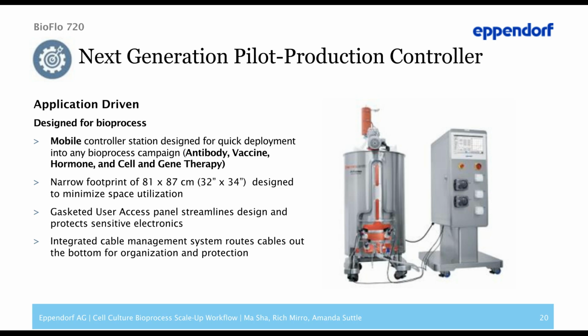The user access panel, shown on the instrument on the left-hand side, closed in the image, streamlines and protects sensitive electronics. In the previous screen, you could see it open where an operator was connecting sensors. That panel allows cables to be routed through an integrated cable management system, and out the bottom, it allows for both organization and protection and ease of cleaning overall for the system.